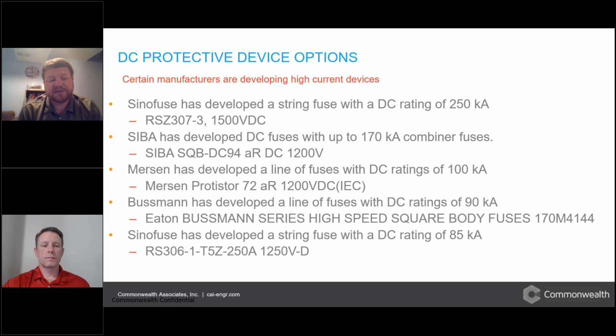So as Chris mentioned with the steady state analysis, we're seeing DC fault currents at almost every location in the DC circuit that's over 80 kA. And most of these DC fuses that you find generally in the market have 50 kA DC ratings. So they won't work. With this list here, we show some examples of devices that have ratings over 50 kA, some as high as 250 kA.